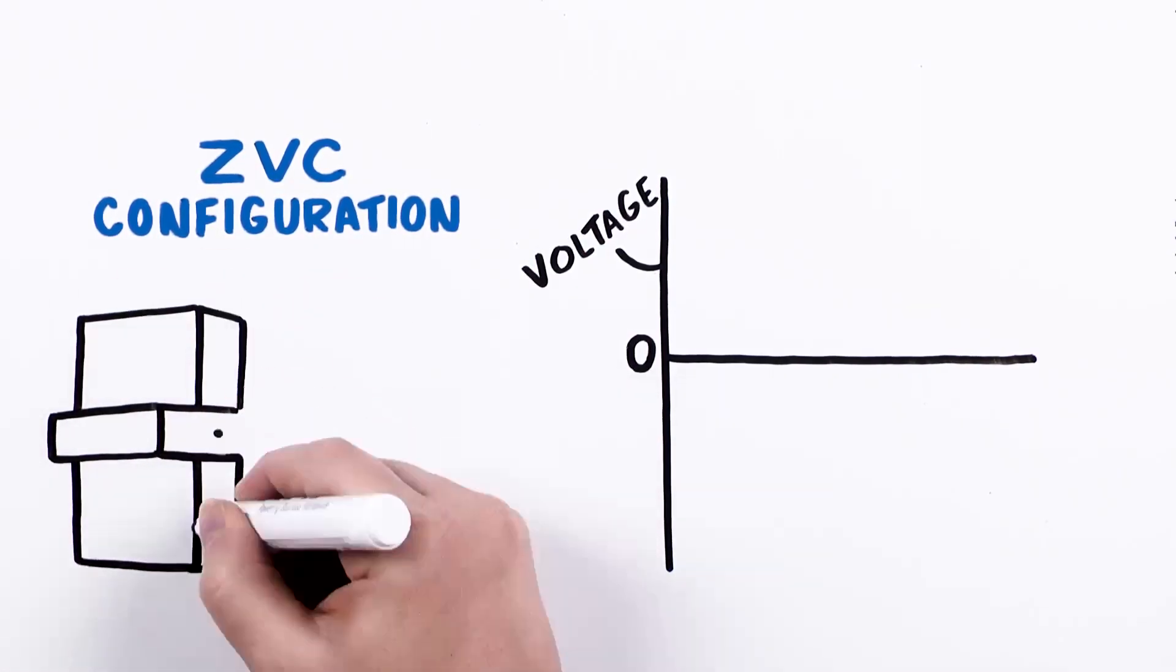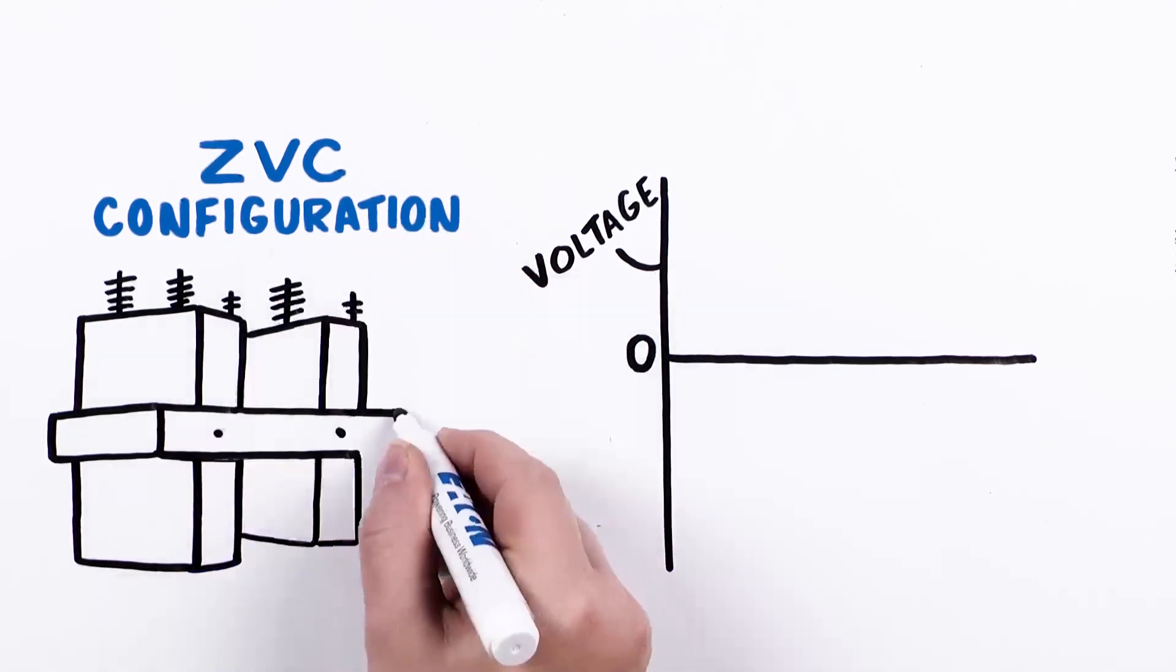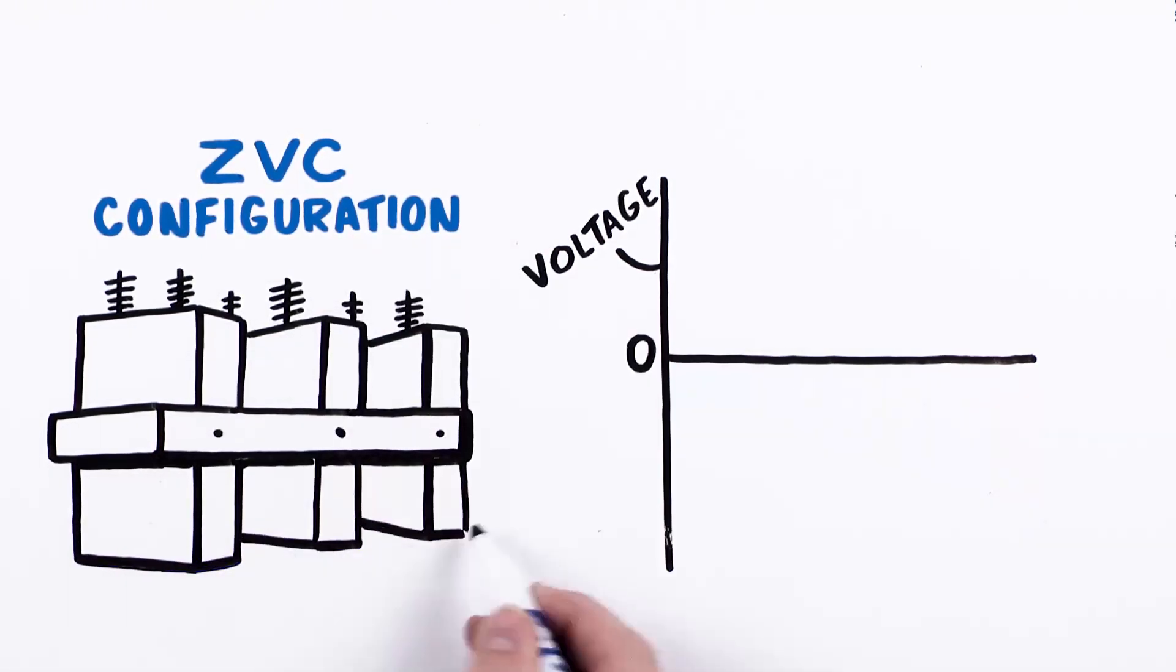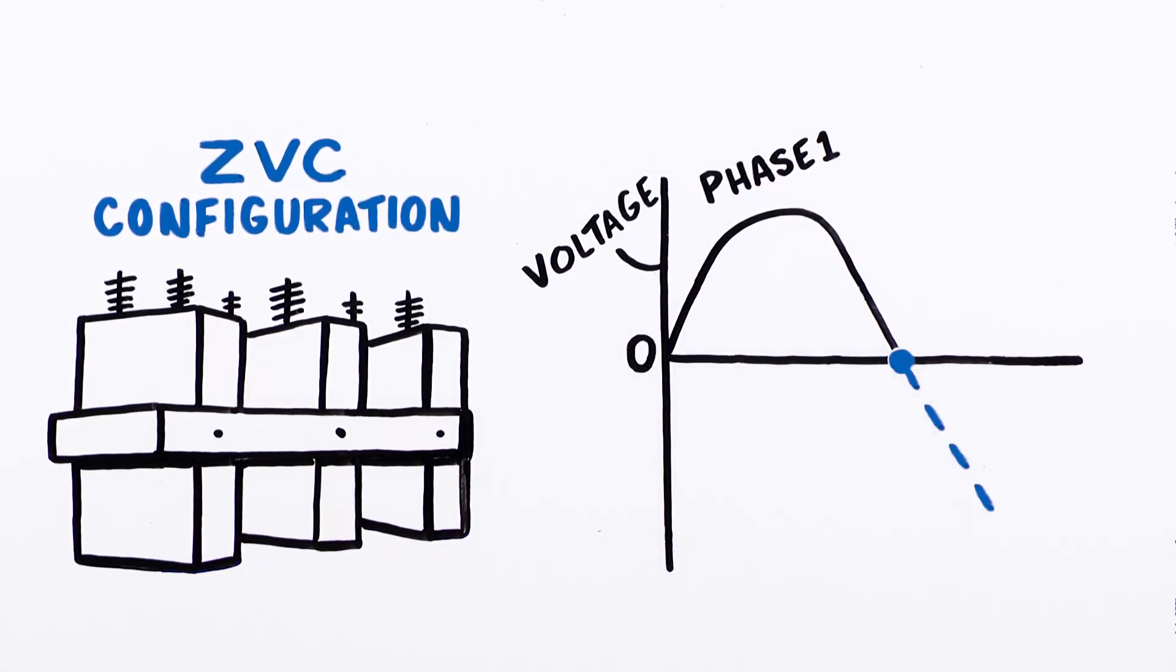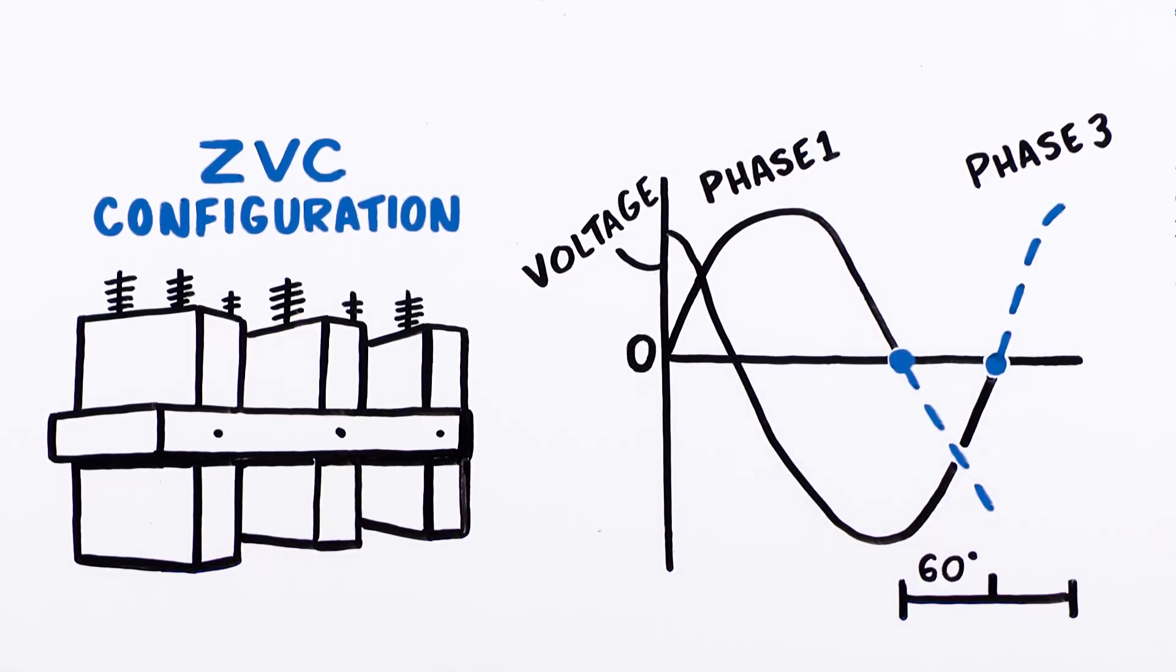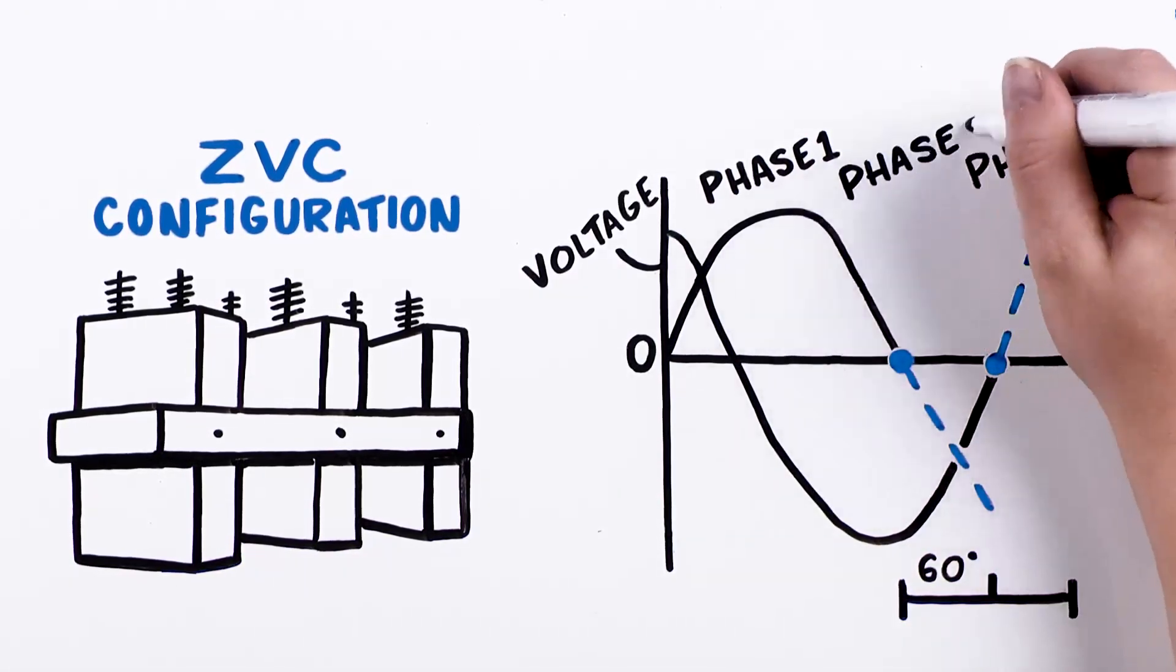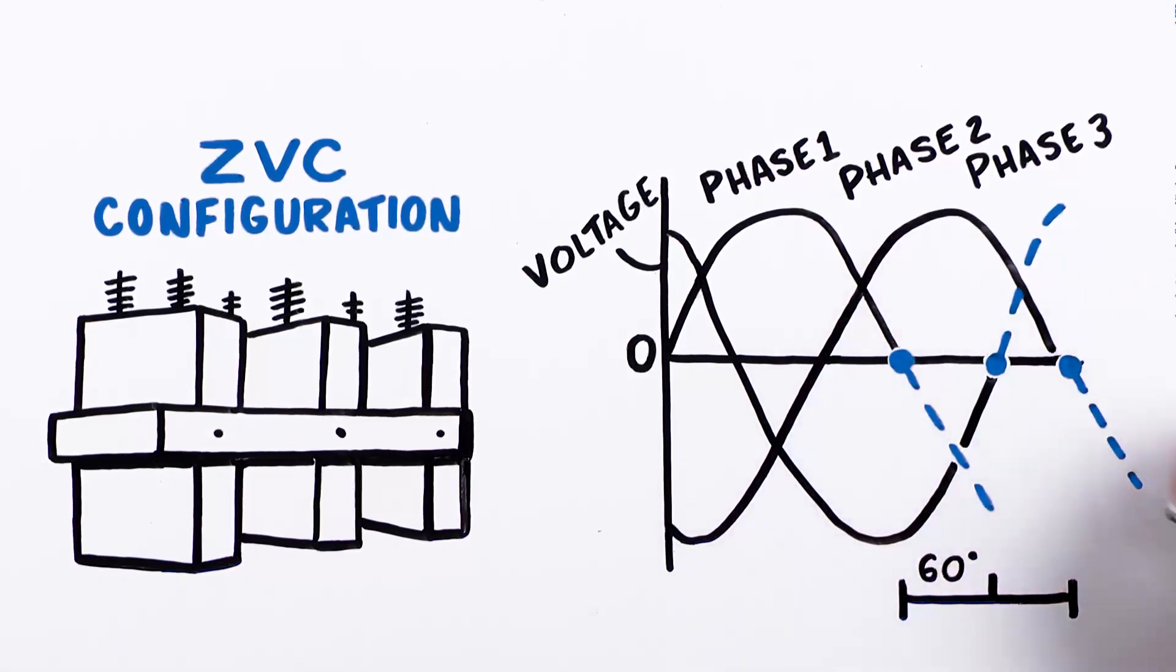Using a grounded Y electrical configuration example, a ZVC configured switch might first close the switch on phase one when it crosses zero. It will then close the switch on phase three 60 electrical degrees later at its zero point, and finally close the switch on phase two 120 electrical degrees after phase one switch is closed.